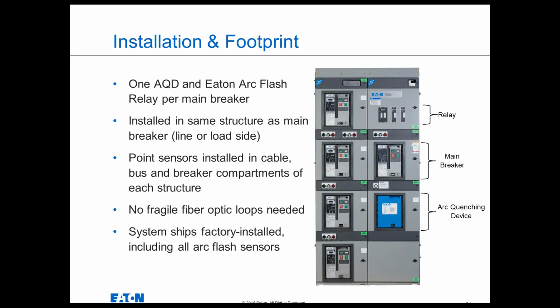Now, if you just have a single-ended lineup, one main breaker, you need one Arc Quenching device and one set of relays. They're installed in the same structure as the main breaker. They can be installed on the line or the load side of that main, and that is an important distinction. I don't have time to get into why that matters, but that is something that warrants a further discussion when we have time.